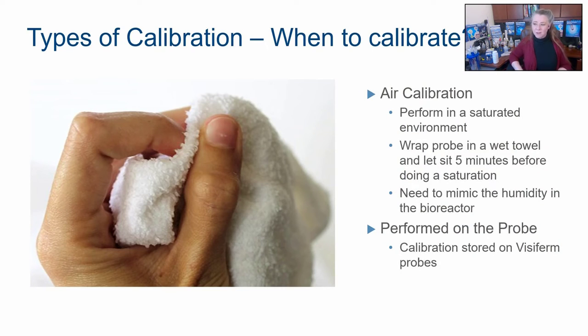How do you do an air calibration? Well, I've talked several times about taking into account humidity. Air calibrations are super easy. Take a wet towel, not a piece of paper towel, but a good amount of wet rag. Wet it, wring it out so it's just a wet rag. Good amount of volume, and you wrap it around the edge of the probe, just like you see in this picture. You put that on the counter, you let it sit for 5 minutes, you say calibrate.